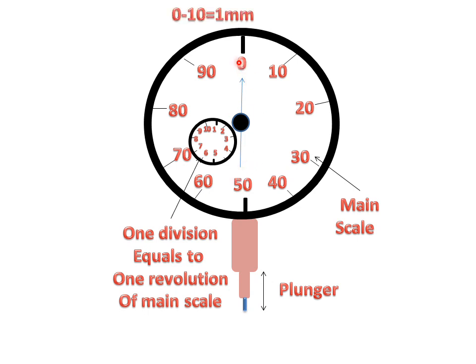This reading 0 to 10 for the main scale is 1 mm. The complete reading 0 to 10 is equal to 1 mm. And the least count of the main scale is 0.01 mm. This means 0.01 mm is the smallest reading we can note from the dial gauge indicator.